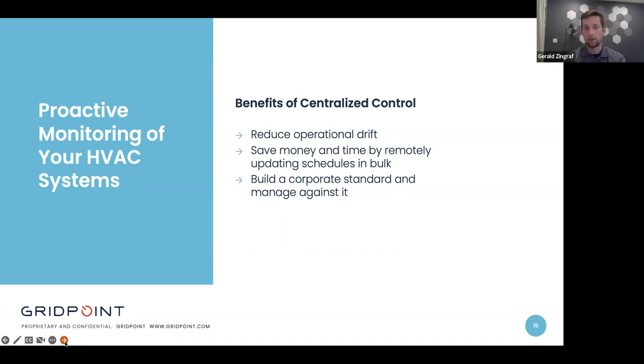The second thing is operational drift. So now that you've got this corporate standard and you've baselined all of your sites against the standard, the schedules, the set points, the overrides, all of that, we need to make sure that we're preventing operational drift. If a thermostat loses power and comes back online, a timestamp gets reset, that contributes to operational drift. If somebody hits permanent hold, that contributes to operational drift. If somebody adjusts the fan mode or the HVAC mode, that contributes to operational drift.